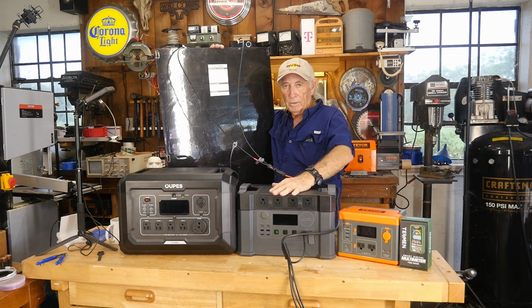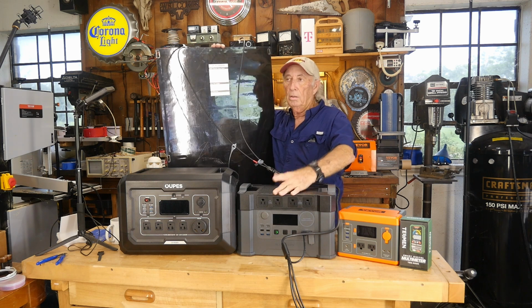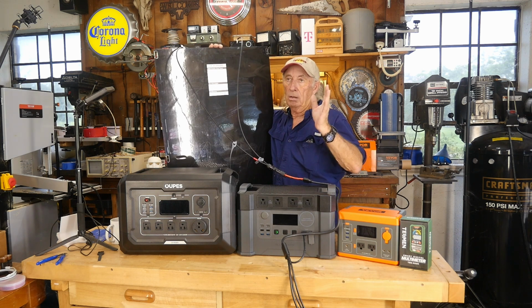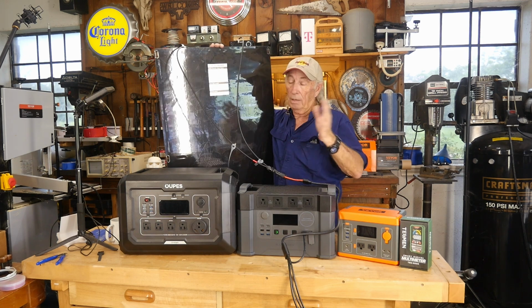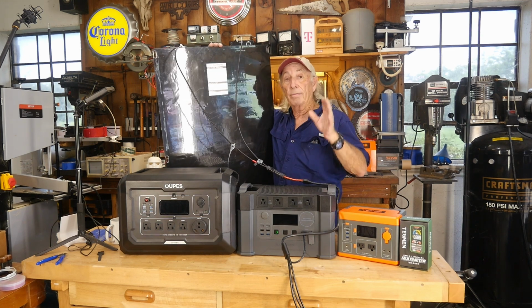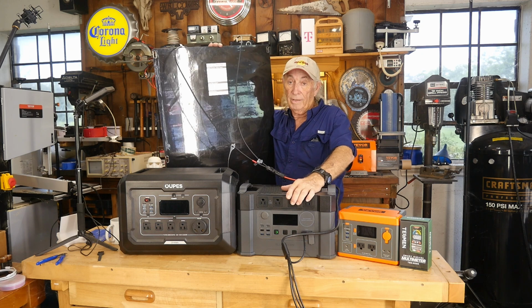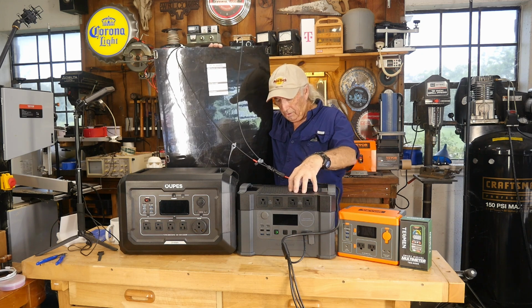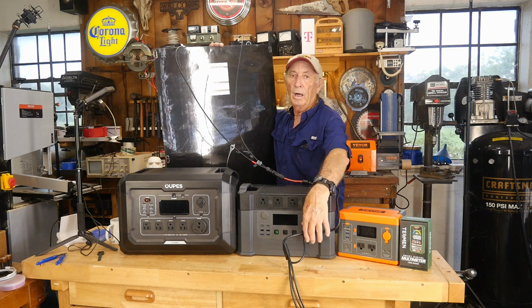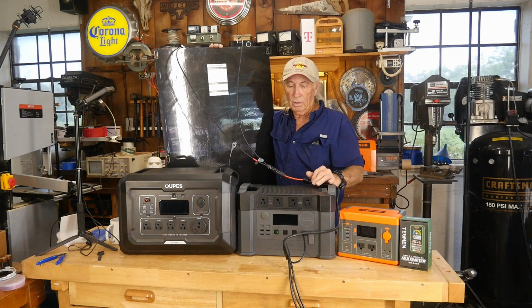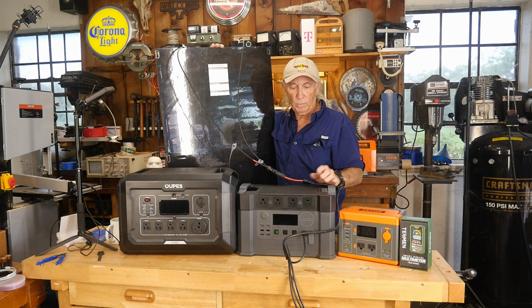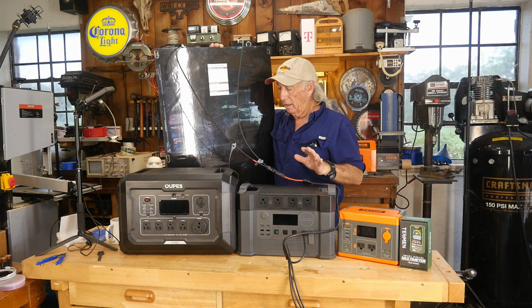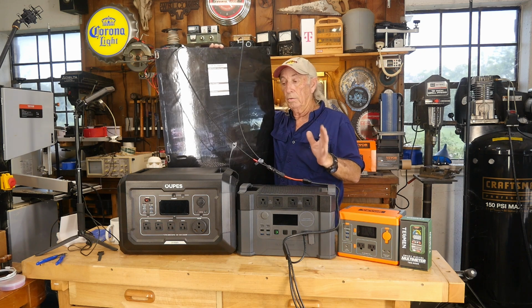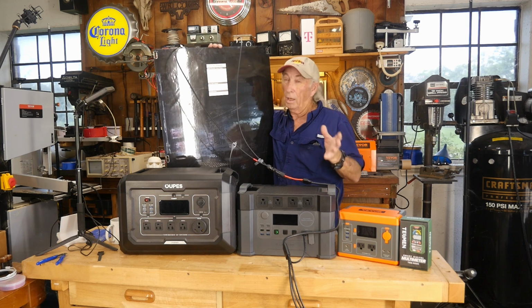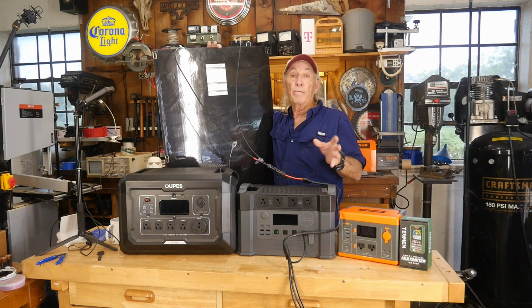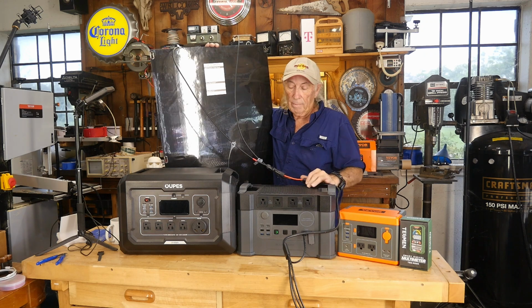When you check your power station, make sure it can handle that voltage range. A lot of them will say something like 11 to 30, 11 to 60, or 11 to 75 volts—it'll be marked on there, or check your service manual. I was checking this All Powers unit this morning and couldn't find a voltage rating for the input, which isn't very good. Usually it's right on the machine, so I'm surprised this one doesn't have it. They generally tell you the voltage range so you don't underload it, which creates a lot of current, heat, and damage, or overload it with too much voltage, which also causes damage.